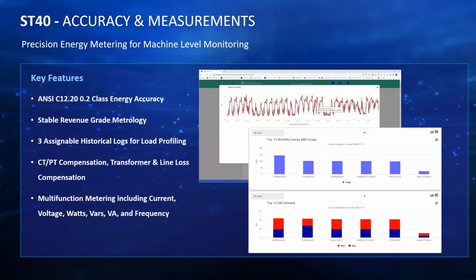We also have 3 assignable historical logs for load profiling. If you were using this meter for billing, you can have billing software look at one log. You can have an engineering department look at another log recording some power quality information. And you can have a third log for any additional parameters you might need to monitor. This is just a partition, a way to keep information separate, so one department doesn't have to sort through information they don't necessarily need.